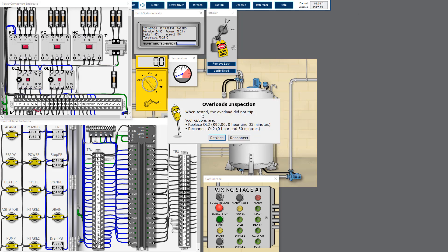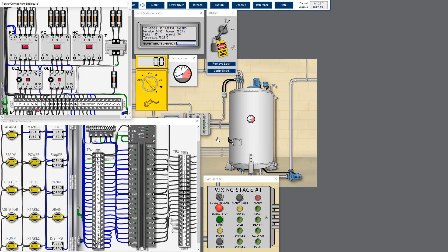Okay, when tested, the overload relay, this confirmed my assumption. So we just need to replace, normalize the multimeter, remove the lockout tagout, and this one, okay, okay.